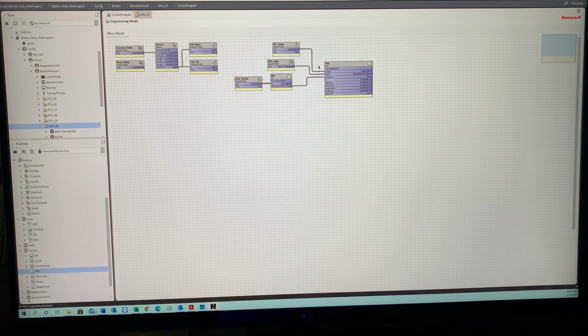We actually had to repair an RTU program based out of a can, where it was looking at just the TR40 SylkBus stat versus the TR70s, which have displays on them. It actually broke several links, and we had to go in and use debug, which brings everything up live so you can see what it's doing. The issue was it would not change between heating and cooling because there was nothing there to show the mode.